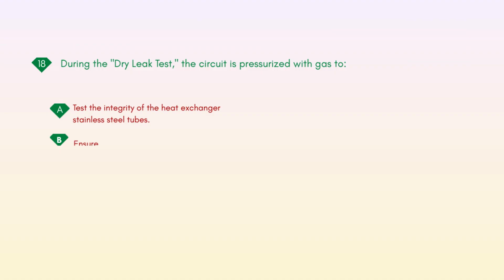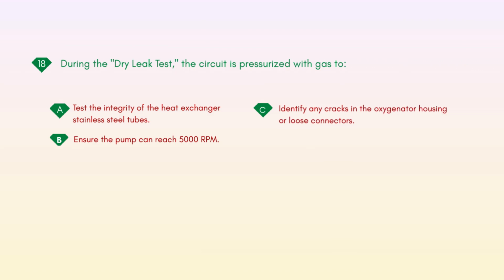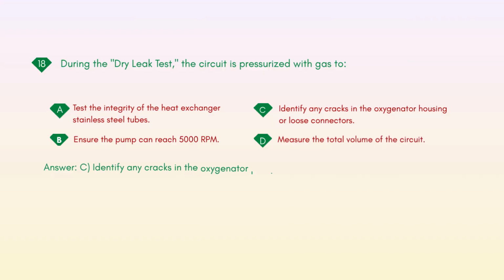During the dry leak test, the circuit is pressurized with gas to A. Test the integrity of the heat exchanger stainless steel tubes. B. Ensure the pump can reach 5,000 revolutions per minute. C. Identify any cracks in the oxygenator housing or loose connectors. D. Measure the total volume of the circuit. Answer: C. Identify any cracks in the oxygenator housing or loose connectors.